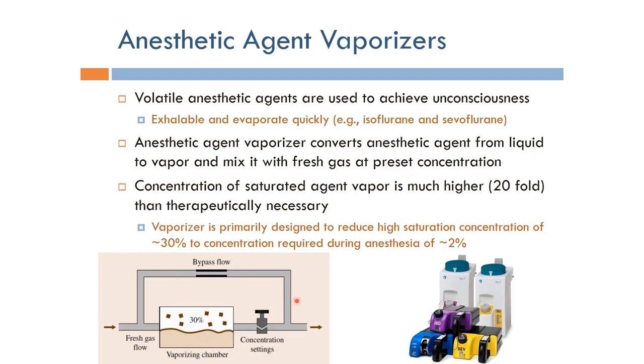This is done by an apparatus that looks like this. We have the anesthetic agents here, and because they evaporate very quickly, the concentration of the anesthetic agent vapor on top will be almost 30%. By passing part of the fresh gas input into the vaporizing chamber and another part through a bypass flow, we control the ratio between the two to get the concentration we need. Vaporizers are primarily designed to reduce this high saturation concentration of nearly 30% down to the concentration required during anesthesia, which is about 2%.